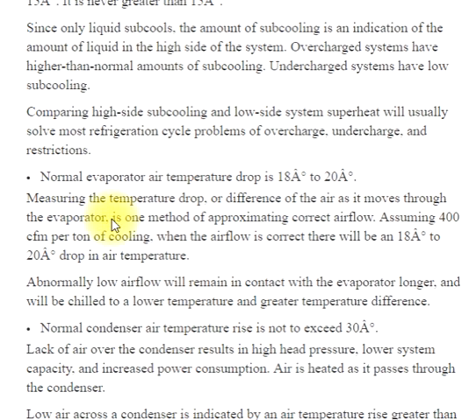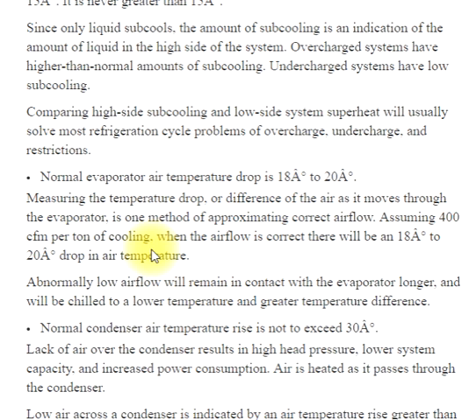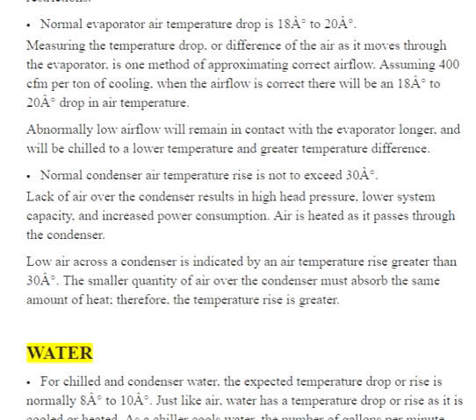Normal evaporator air temperature drop is 18° to 20°. Measuring the temperature drop of the air as it moves through the evaporator is one method of approximating correct airflow. Assuming 400 CFM per ton of cooling, when the airflow is correct there will be an 18° to 20° drop in air temperature. Abnormally low airflow will allow air to remain in contact with the evaporator longer and will be chilled to a lower temperature, resulting in a greater temperature difference.